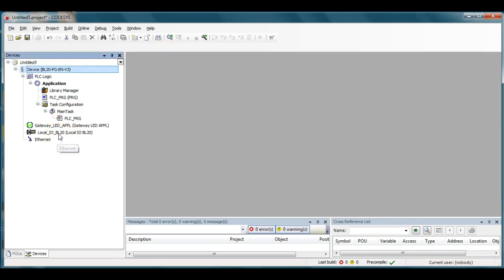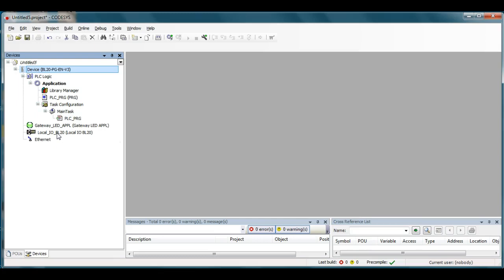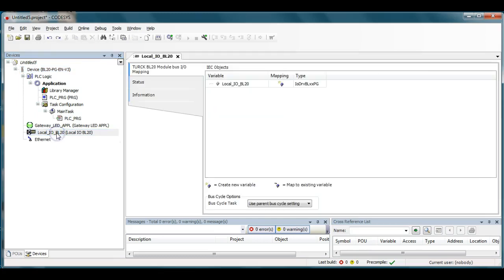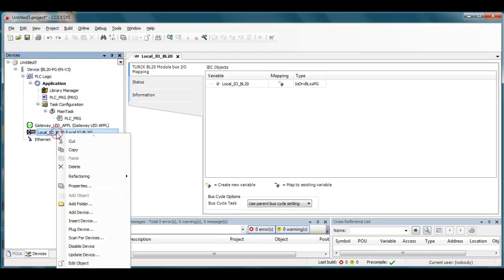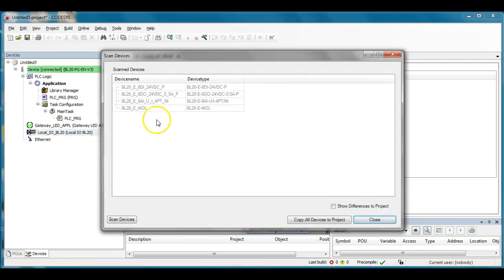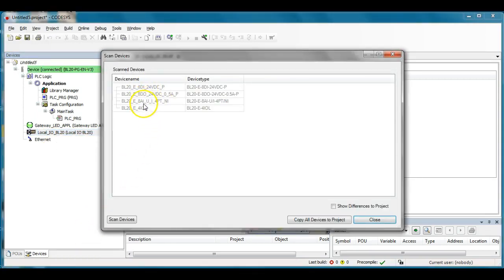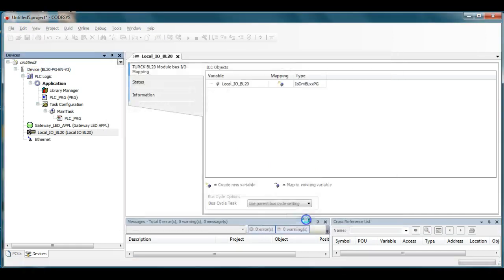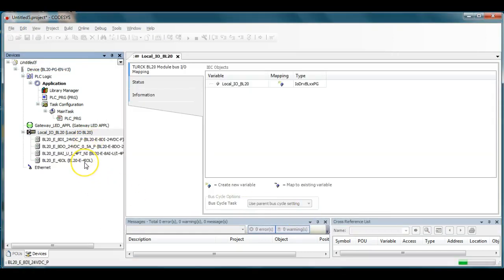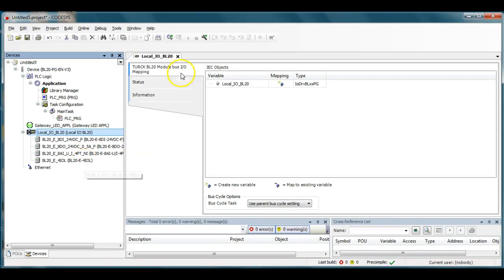I also would like to scan the local IO just to see what's connected to the Turk BL20. So I'll double-click here on the local IO rack. Actually, I guess I should right-click is what I should do and scan for devices. It's going to go out and it finds that I currently have four cards plugged into this: an 8 digital in, 8 digital out, 8 analog in, and 4 IO with IO link on it. And let me go ahead and hit copy all devices to project which will then bring in all those particular slices. Excellent.